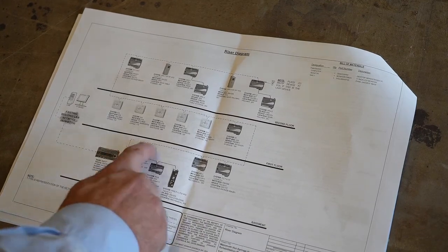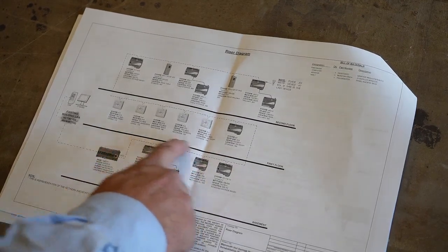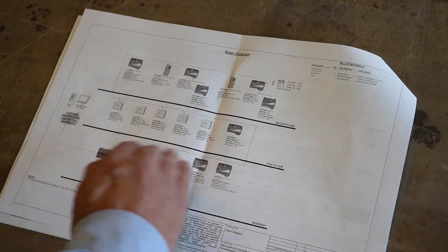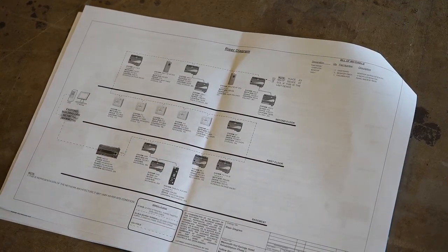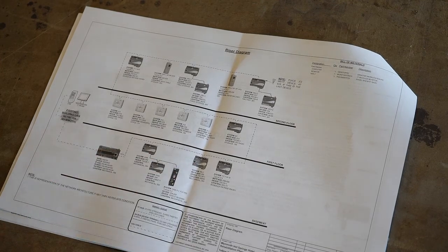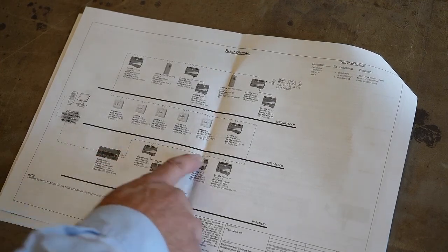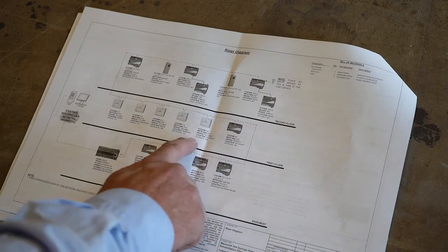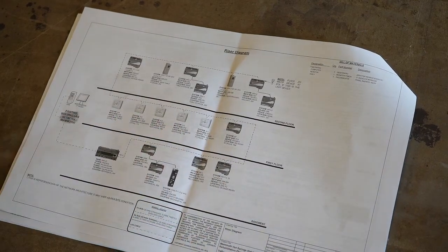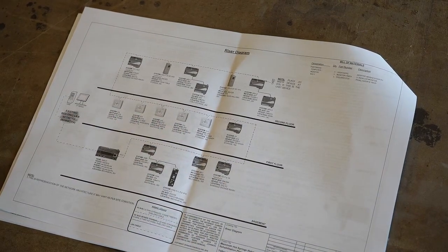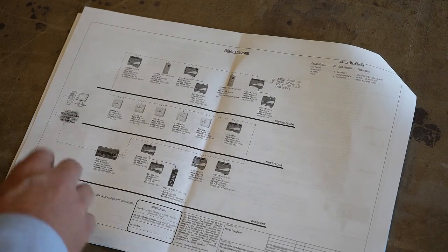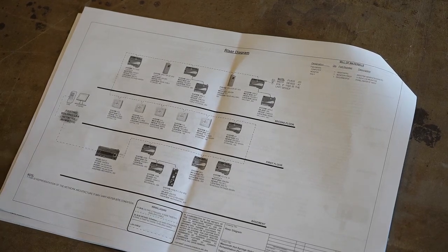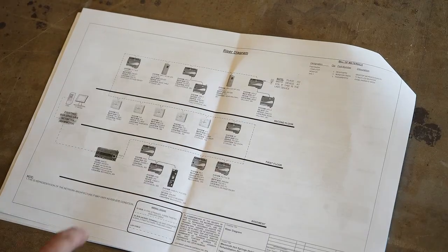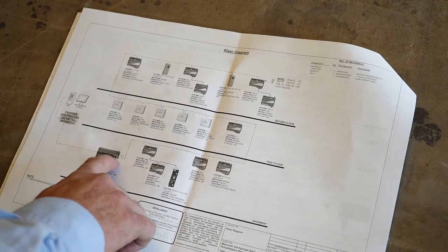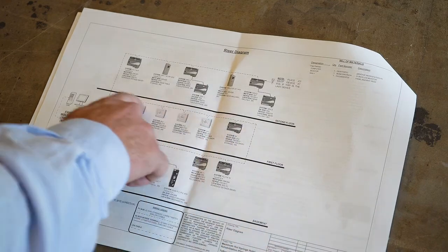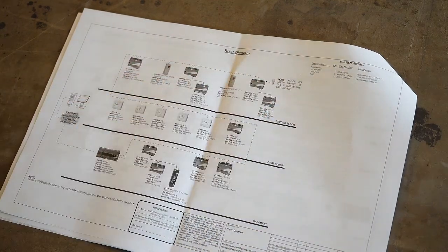Now, it doesn't necessarily go to this one first and then to this one. It could go over to here, back to here, but it's a representation of what's on the trunk and in what area. So this line connects to every one of our controllers. We do have some TEC thermostats located on the different floors. They have an LCD display on them. All right, so our FEC trunk will come off the NAE and then it'll daisy chain to every individual device that we're controlling.